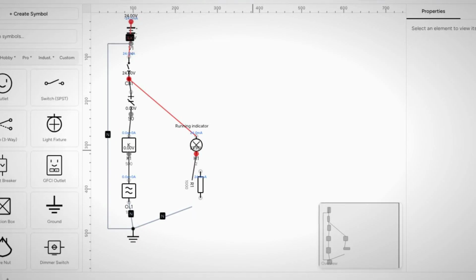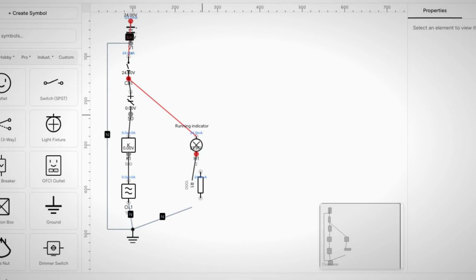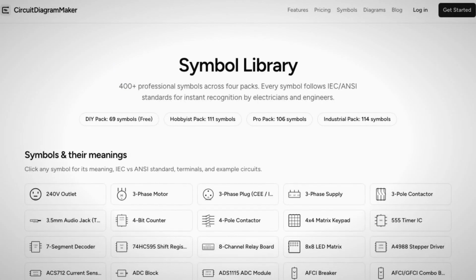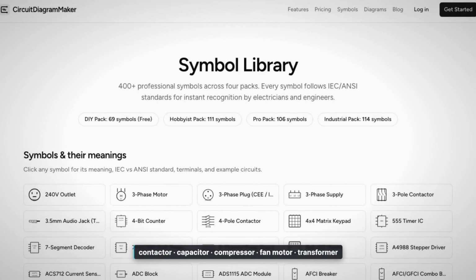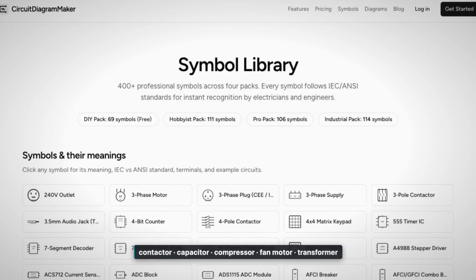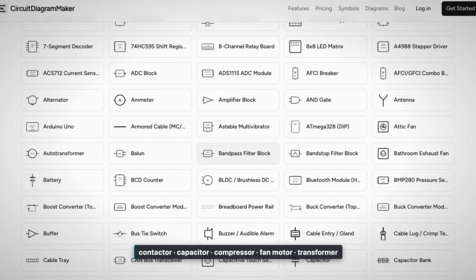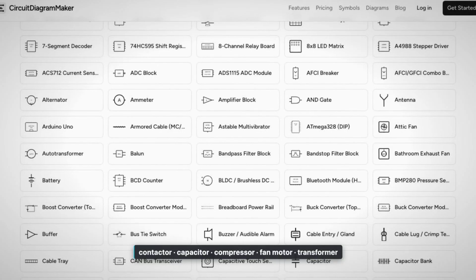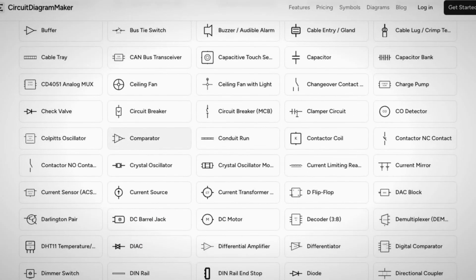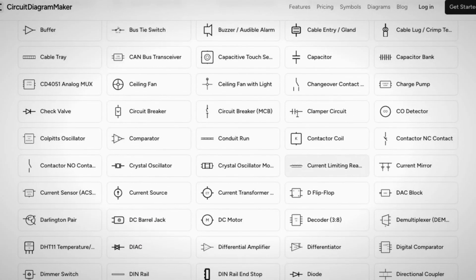One more thing worth knowing, the symbols. HVAC prints reuse the same handful of shapes. The contactor, the run capacitor, drawn as two lines. The compressor, the fan motor, a circle with an M. The limit switch, and the transformer, those two coils. Learn 6 shapes, and most of the page reads itself.